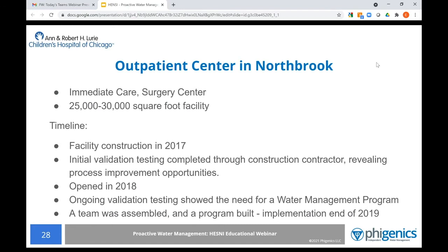During our construction water management and validation testing, we really struggled to achieve negative Legionella and total heterotrophic aerobic bacteria, or THAB, test results. This was probably due to the vendors or the contractors not following their plan. But we determined through a risk assessment, which considered the building layout, the use of the building, along with the construction water quality problems we had, that a water management program would be built for this facility, which included assembling an independent water management team to oversee the program. Next slide.